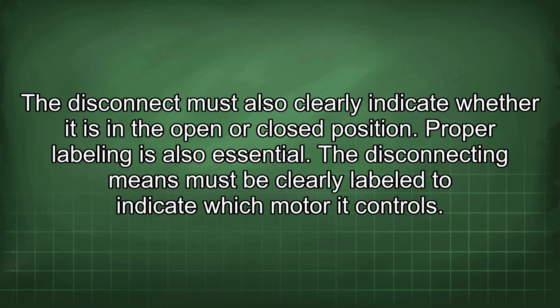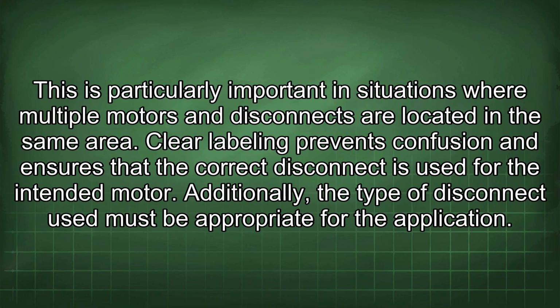Proper labeling is also essential. The disconnecting means must be clearly labeled to indicate which motor it controls. This is particularly important in situations where multiple motors and disconnects are located in the same area. Clear labeling prevents confusion and ensures that the correct disconnect is used for the intended motor.